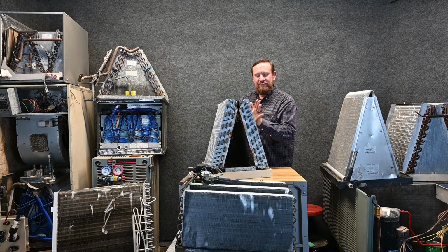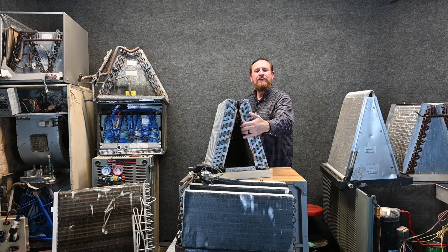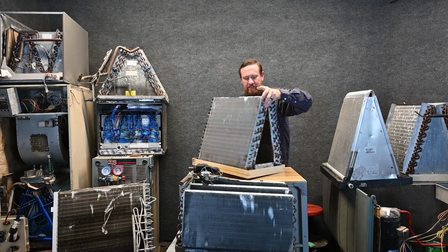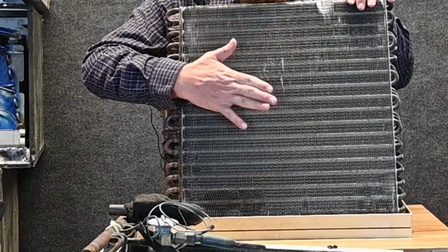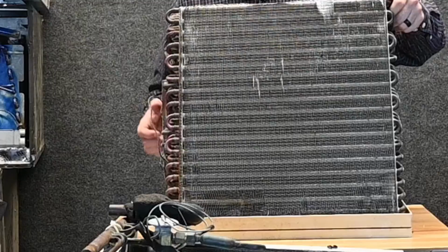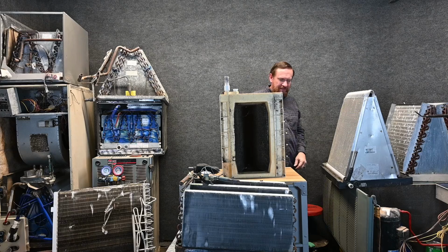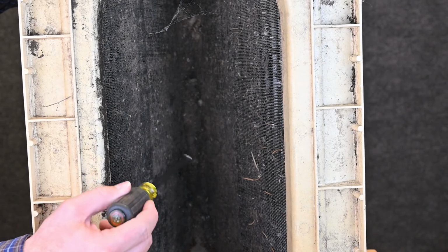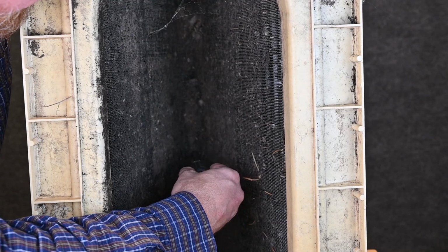What you need to check is not this side of the coil, but the underside of the coil. So this coil, if we look, ultimately it's very shiny. It looks like it's in pretty good shape. We say, hey, it looks fantastic. Let's take a look on the underside and see what it looks like. So one side looked like it was great, but if you look inside of this one, it's absolutely disgusting.